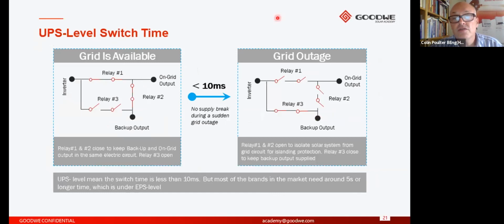So I'd just like to return back to a bit of information about the UPS level switch time. All this is showing is that we are compliant with G98, G99. So when the inverter is on grid, you can see here by virtue of relay 1 and relay 2 being closed, we do get power from the grid available to the on-grid supply of the inverter and the backup supply of the inverter. But relay 3 is open, so there is no direct connection between the backup side and the on-grid side from the inverter output power.